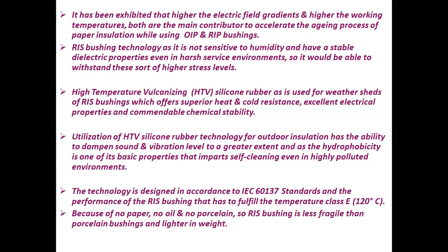The technology is designed in accordance with IEC 60137 standards, and the RIS bushings have to fulfill temperature class E, that is 120 degrees centigrade. Because of no paper, no oil, and no porcelain, RIS technology is less fragile than porcelain bushings and lighter in weight. In case of RIP bushings, the temperature class is B type, that is less than 120 degrees centigrade.